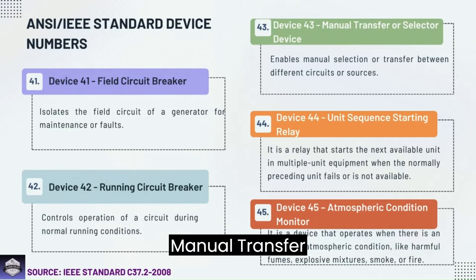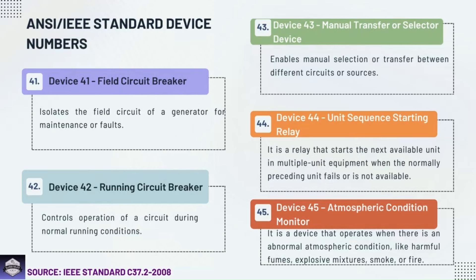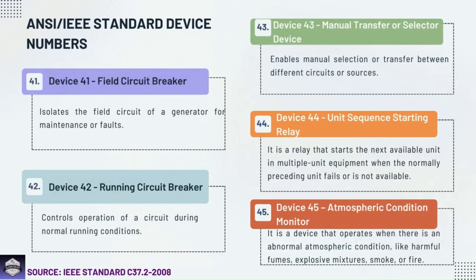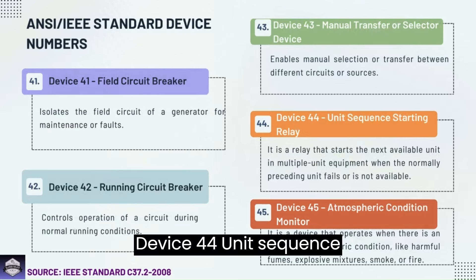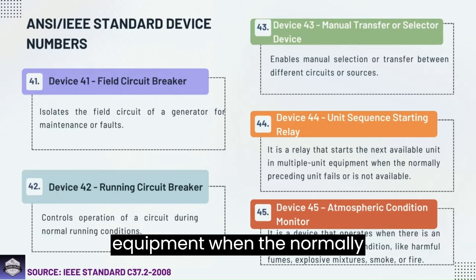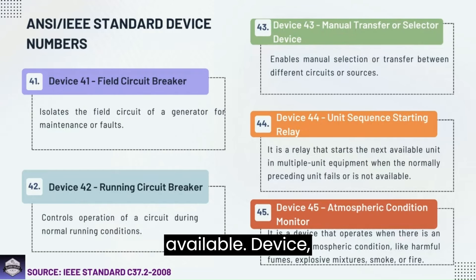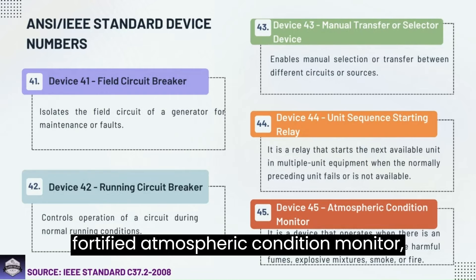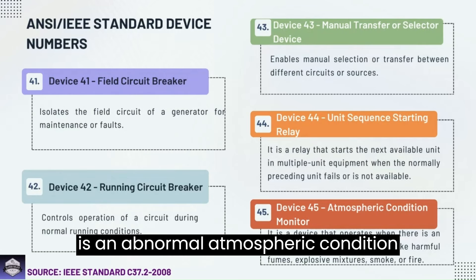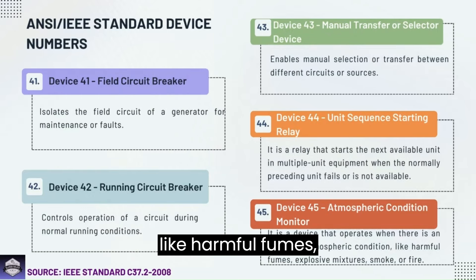Device 43: Manual transfer selector device — enables manual selection or transfer between different circuits or sources. Device 44: Unit sequence starting relay — a relay that starts the next available unit in multiple unit equipment when the normally preceding unit fails or is not available. Device 45: Atmospheric condition monitor — operates when there is an abnormal atmospheric condition like harmful fumes, explosive mixtures, smoke, or fire.